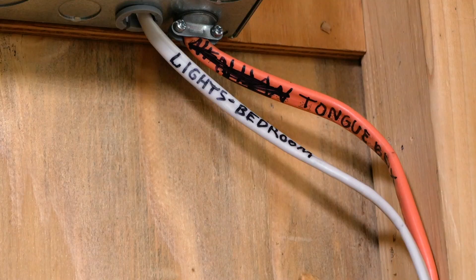Back to our electrical loads here. We've got the first breaker. This is a 30 amp normal breaker, but it's going to end up being a 20 amp breaker, and that's going to feed my outdoor outlet, which is actually just going to have a GFCI outlet on it because that's the simplest and cheapest way to do this. I'm not worried about ArcFault in this case because it's a dedicated run, with only a connection at the box and a connection here, so there's a pretty minimal chance of creating arc faults.